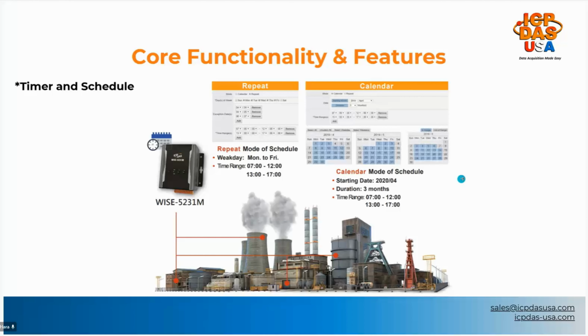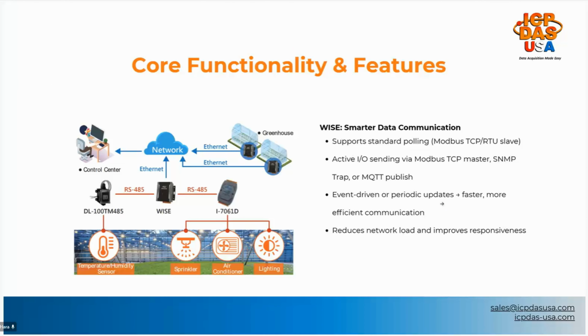WISE doesn't wait to be polled over Modbus TCP or RTU. It also supports active I/O sending, meaning it can push data directly using Modbus TCP master, SNMP trap, or MQTT publish. With this approach, WISE can immediately send I/O updates to SCADA, IT, or IoT systems whenever values change or at defined intervals. This event-driven communication reduces unnecessary polling traffic and improves the overall efficiency and responsiveness of your system.